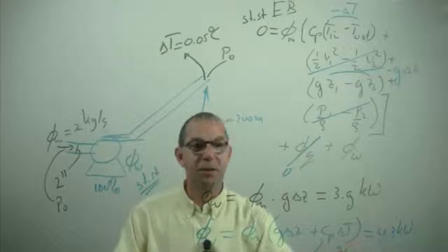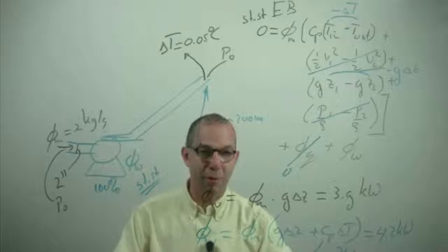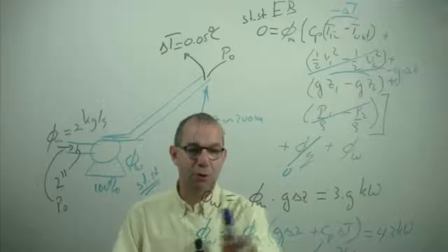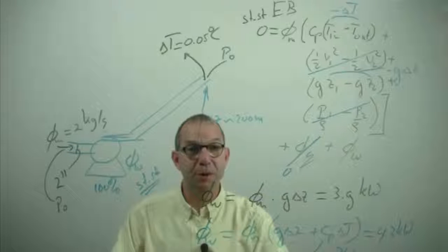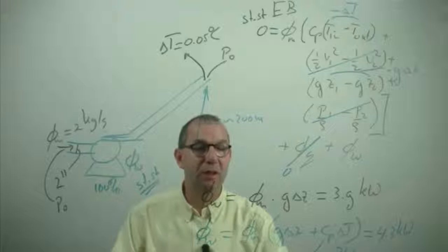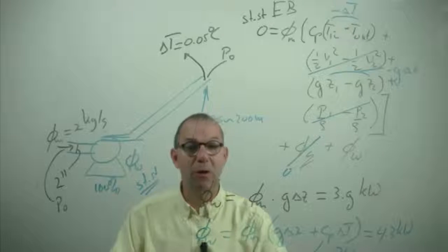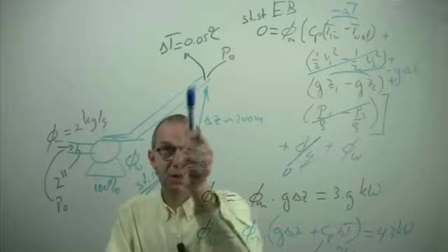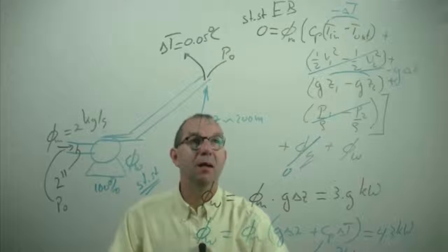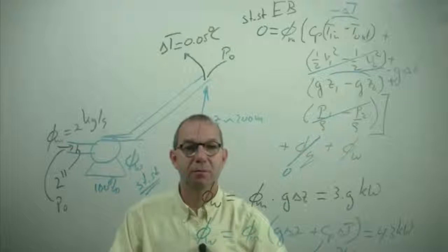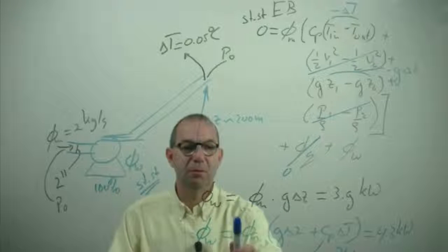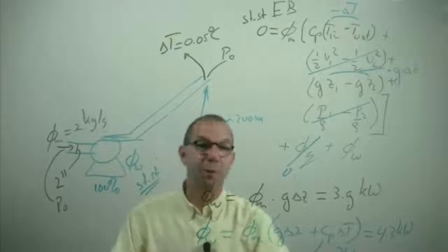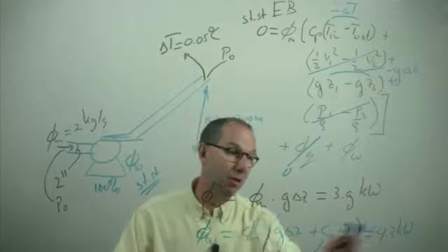Okay, 10%, is that much or is that little? Well, it's not too bad, but it's a loss term that is there. Moreover, your pump will probably have to be a little bit stronger. It needs to supply a little bit more power, as we assume that everything that a pump generates is turned into energy that is useful in this equation. In practice it's not. The pump will heat up itself, and there's a loss term. So the efficiency of the pump is less than 100%, and you need a heavier pump.